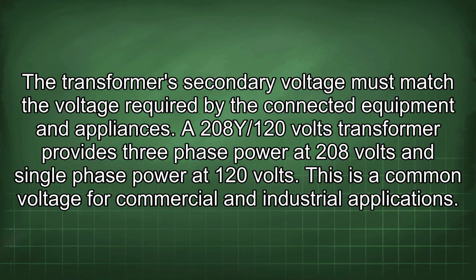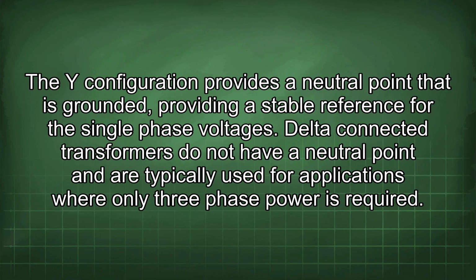A 208Y/120 volts transformer provides three-phase power at 208 volts and single-phase power at 120 volts. This is a common voltage for commercial and industrial applications. The Y configuration provides a neutral point that is grounded, providing a stable reference for the single-phase voltages.